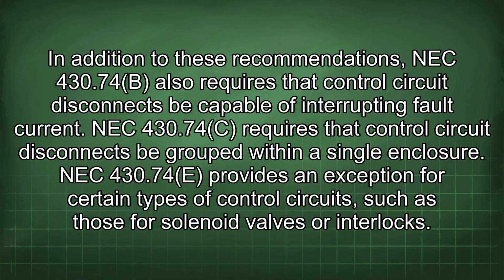NEC 430.74 C requires that control circuit disconnects be grouped within a single enclosure. NEC 430.74 E provides an exception for certain types of control circuits, such as those for solenoid valves or interlocks.